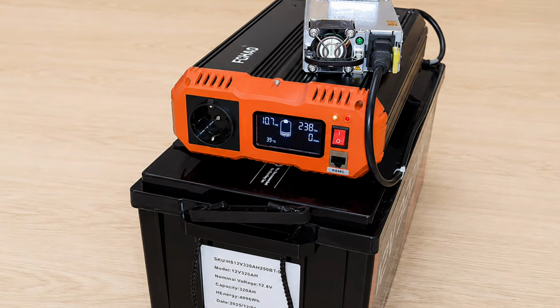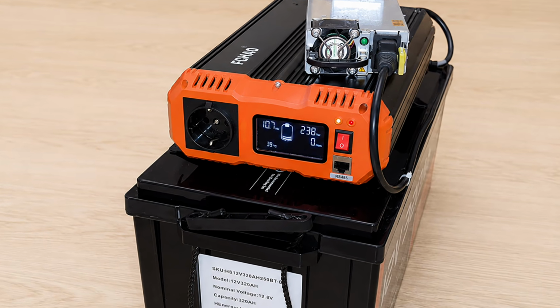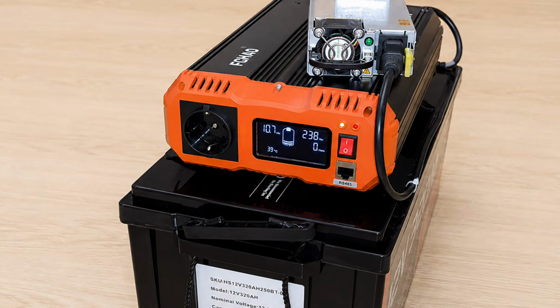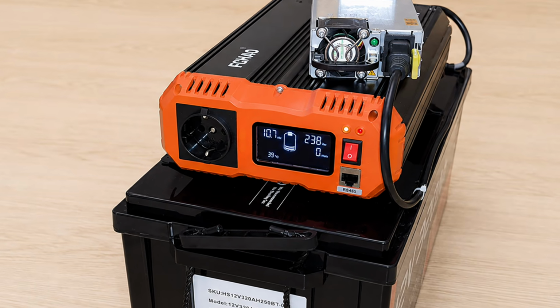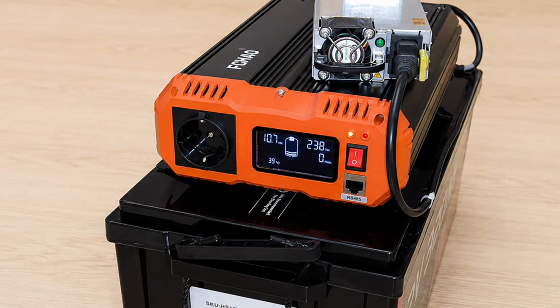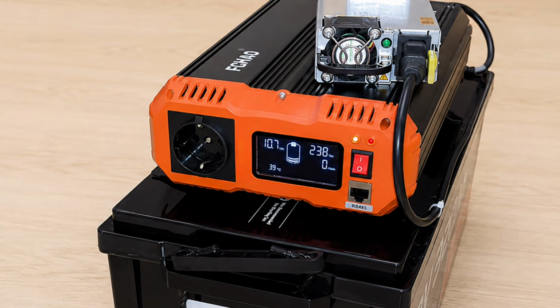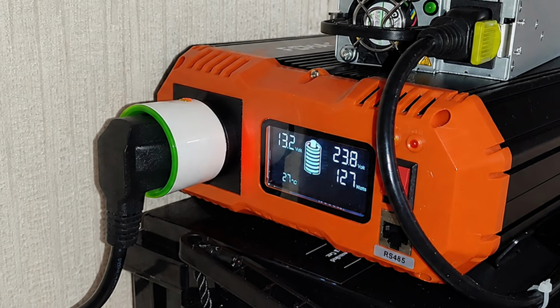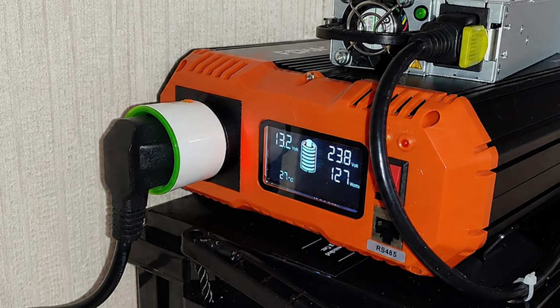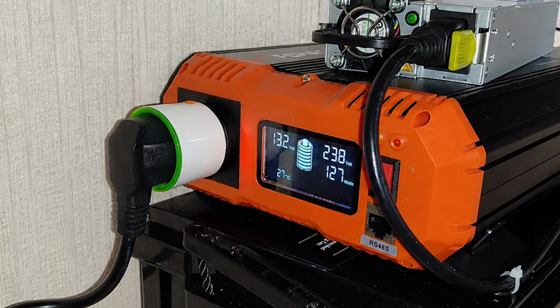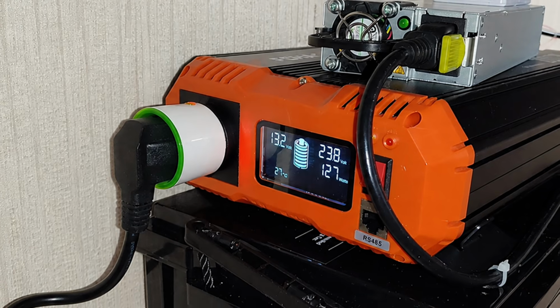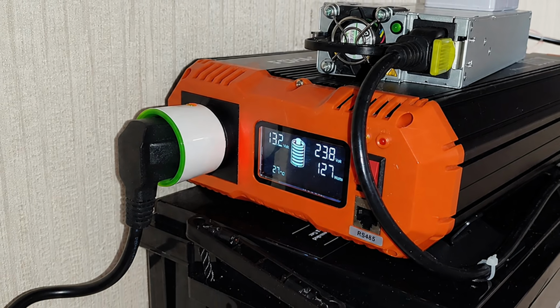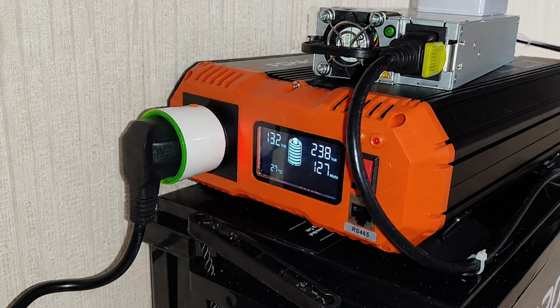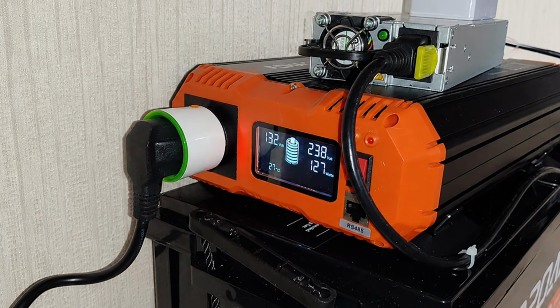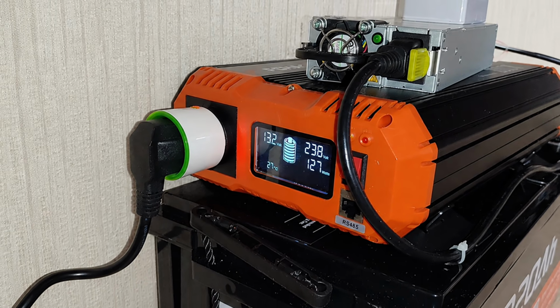Without load, the inverter was able to start, although the battery showed a 0% charge level. Even the cooling fans worked for some time, until its temperature dropped. According to the BMS, active ventilation consumes about 20 watts. One more observation when using it as a backup power source for low power loads, up to 200 to 300 watts. Most of the time, the inverter operates silently, but the screen shows that the temperature is gradually rising. The higher the load and the ambient temperature, the faster the inverter temperature rises.